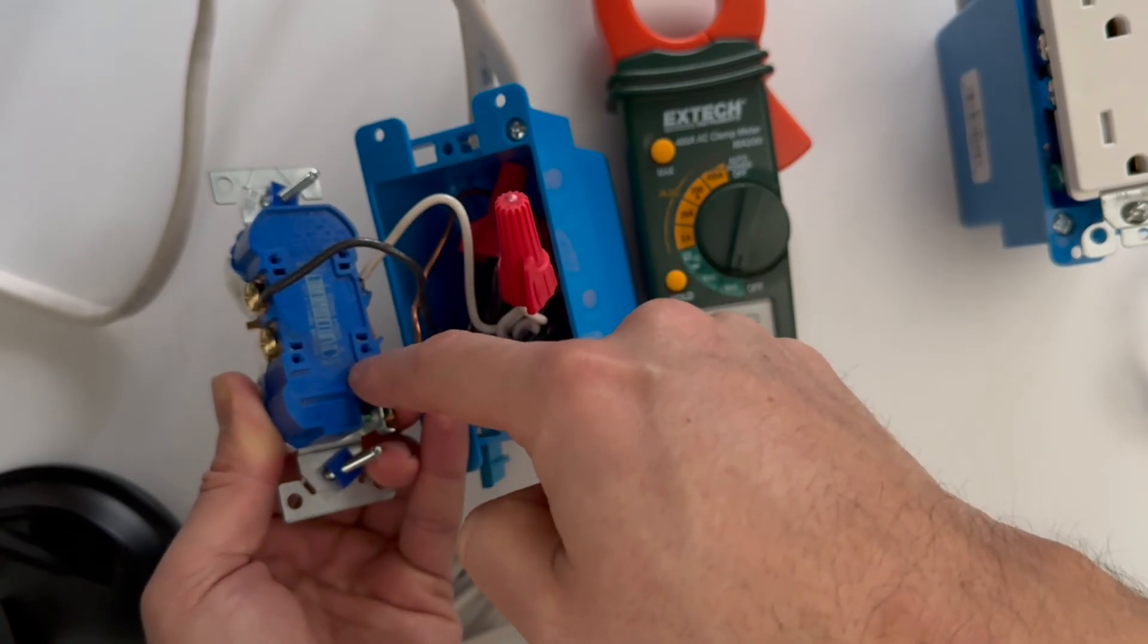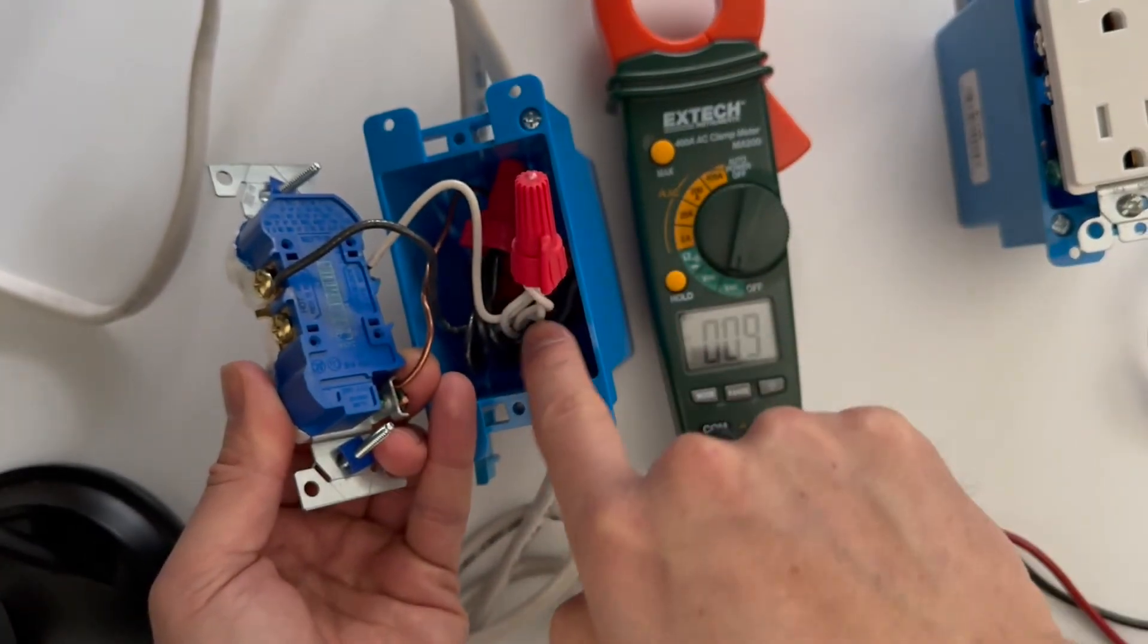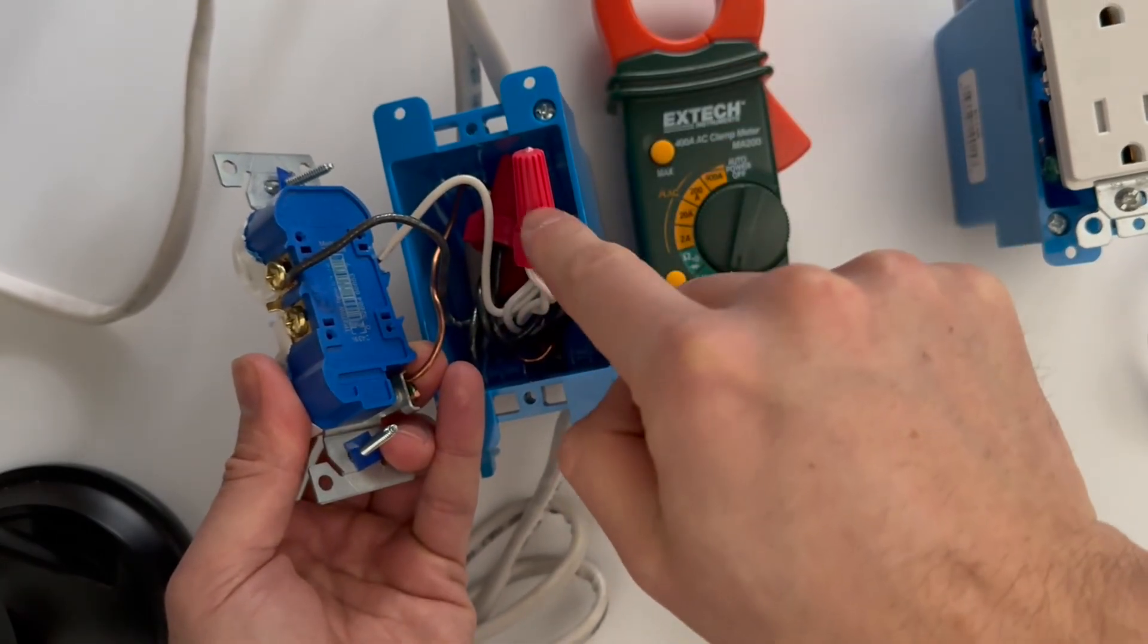It fails either inside of the outlet when you backstab it, and you will usually notice it will become dark or burnt out, or it will fail in the pigtailing connection.